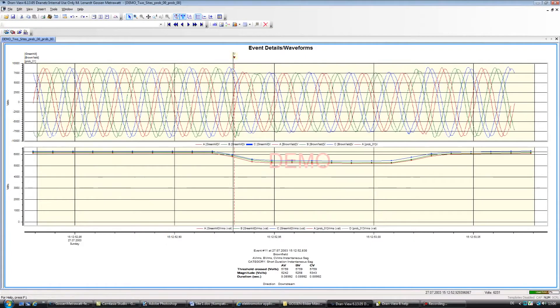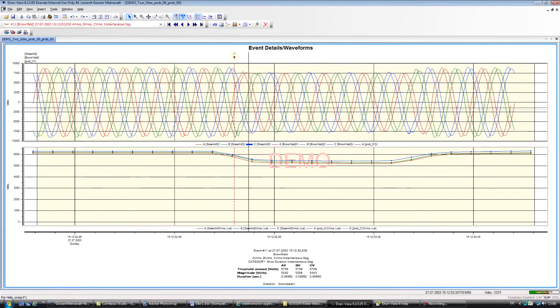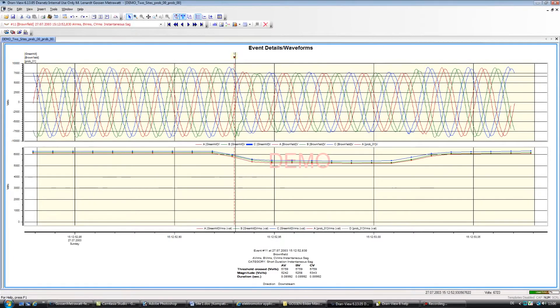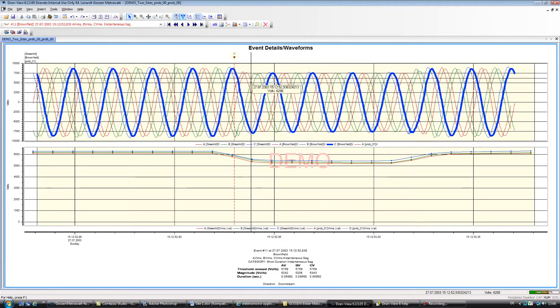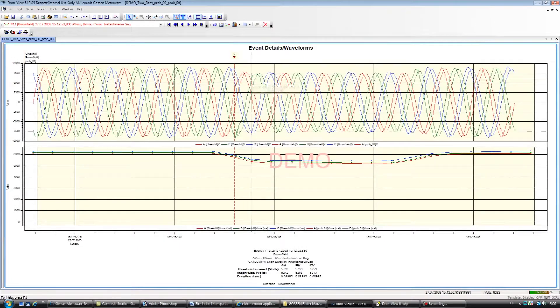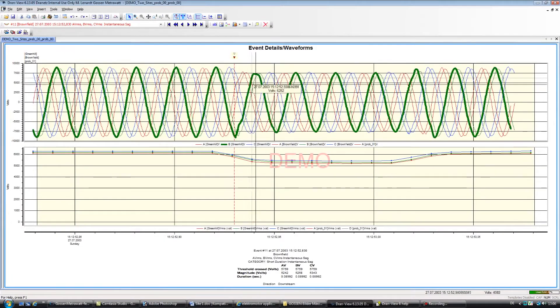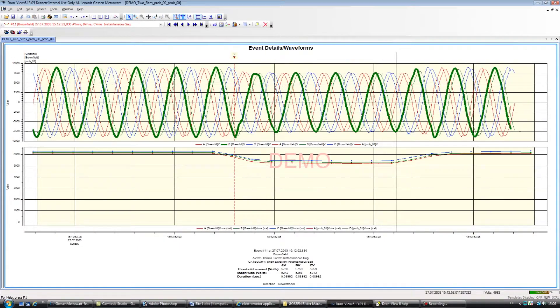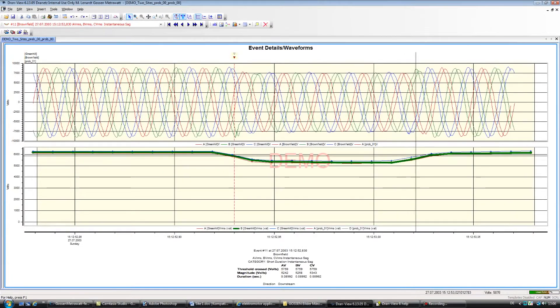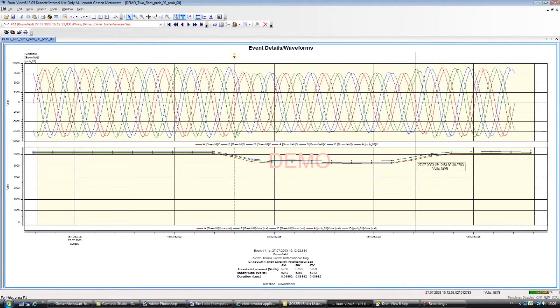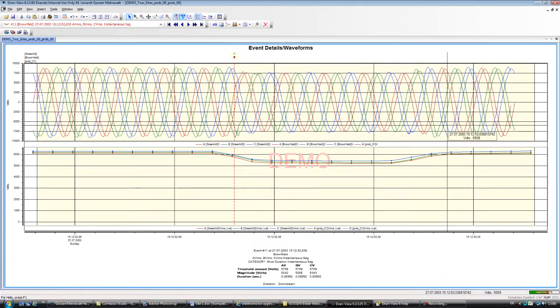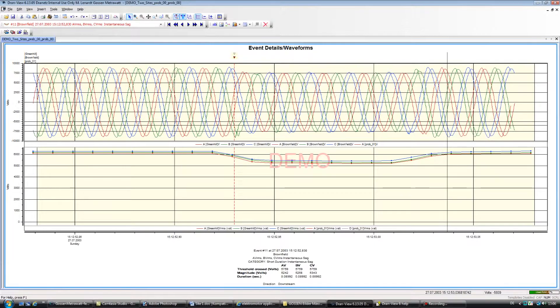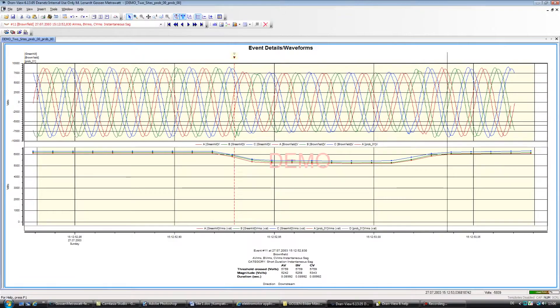In such cases, the objective of the survey is to directly compare input and output data. A much more convenient method is found in the multi-site feature of DranView Enterprise. With the multi-site feature, you can overlay data from multiple sites on one trend or waveform display and even adjust the x-axis or time to make sure that they're synchronized.